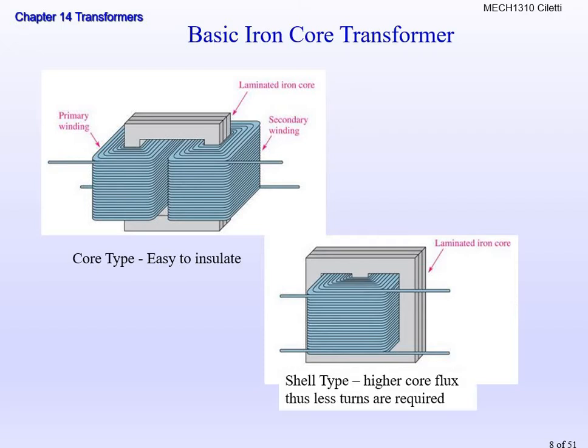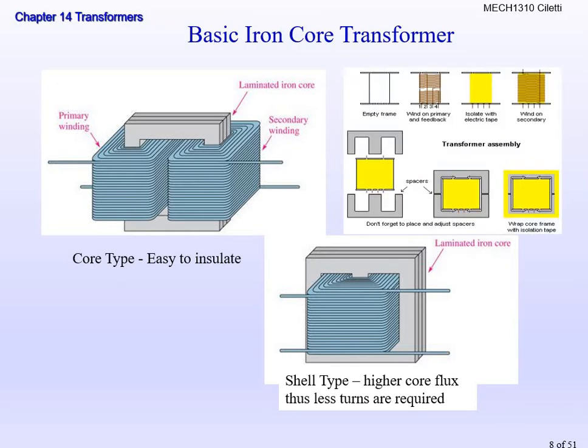With a shell type, we get a higher core flux, meaning a stronger magnetic field, so we don't have to make as many turns. That's the advantage of a shell type transformer—you don't need as much wire. But it's a little harder to insulate since it's wrapped around the middle. You can see a breakdown of what it looks like and how it goes together. I'll try to bring one or two in so we can look in class.